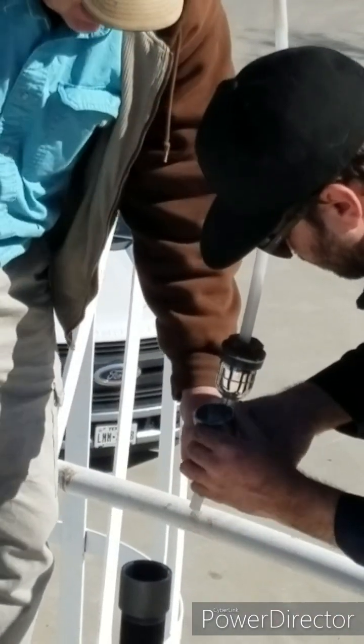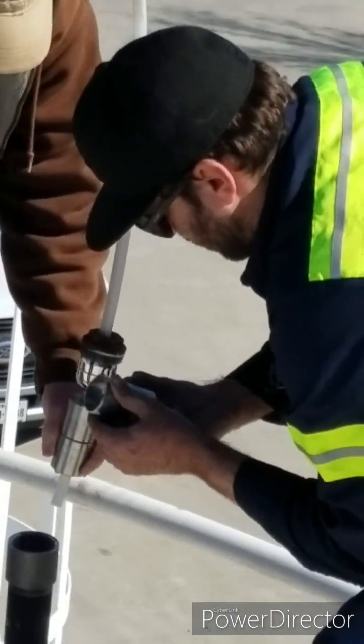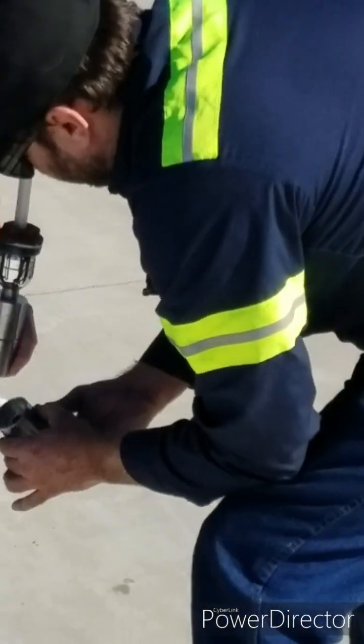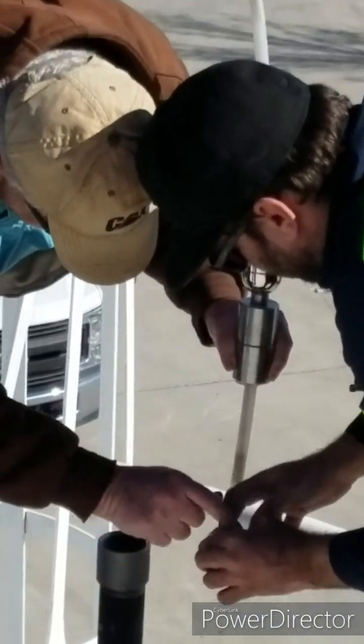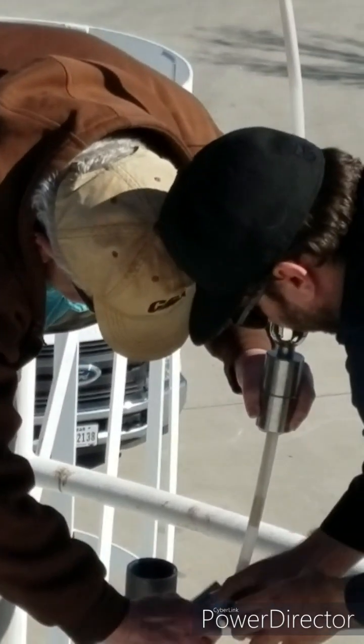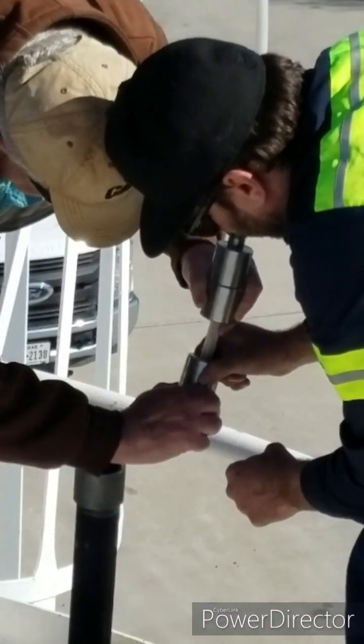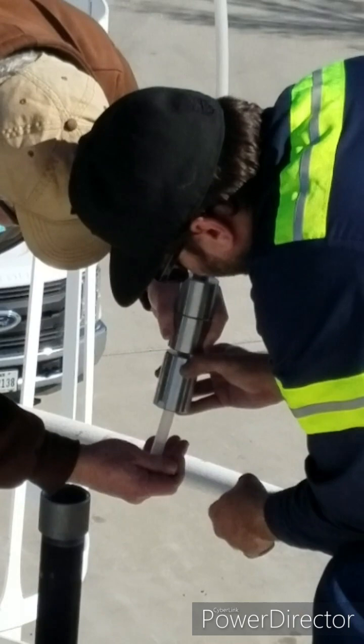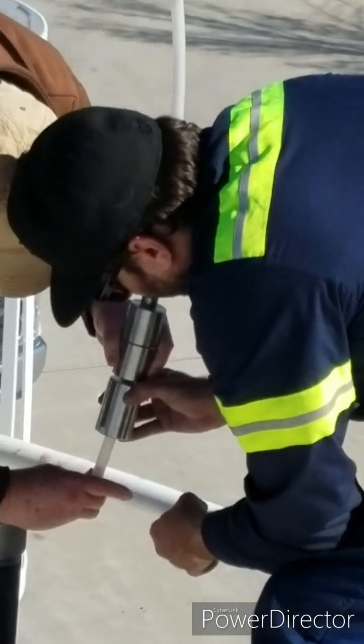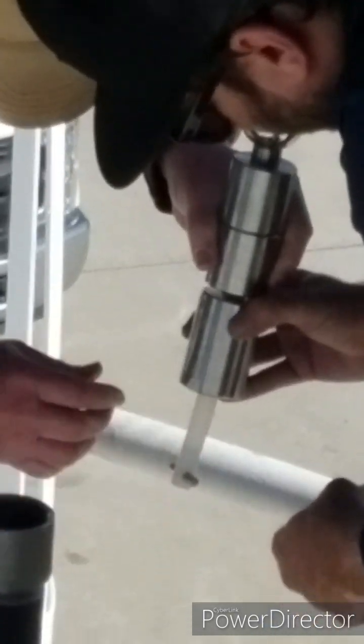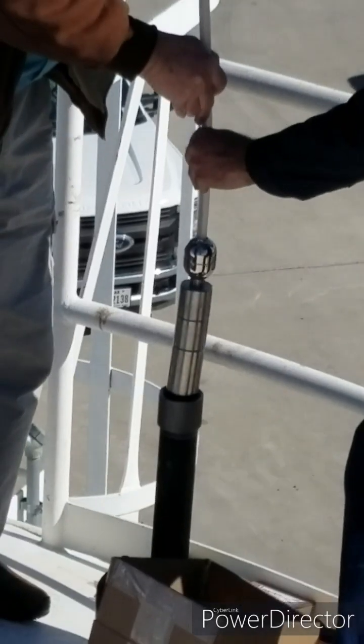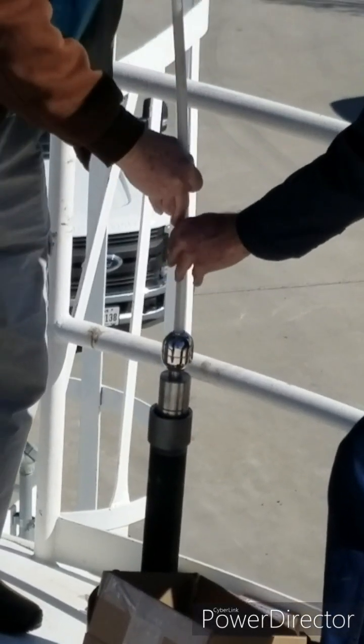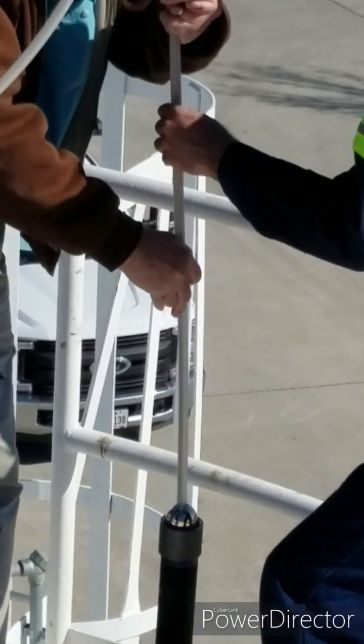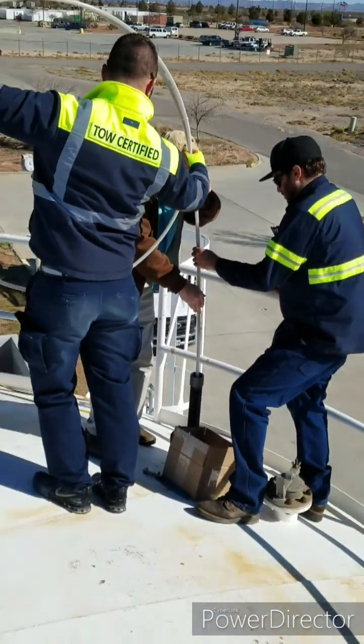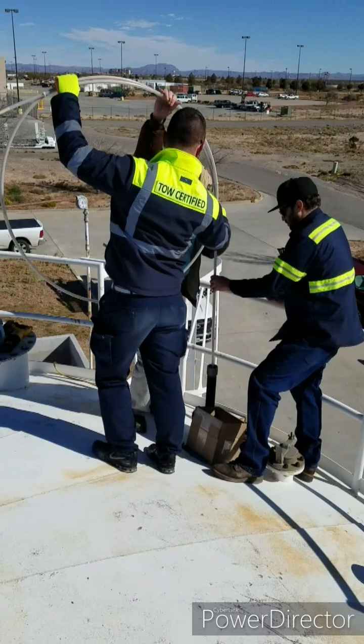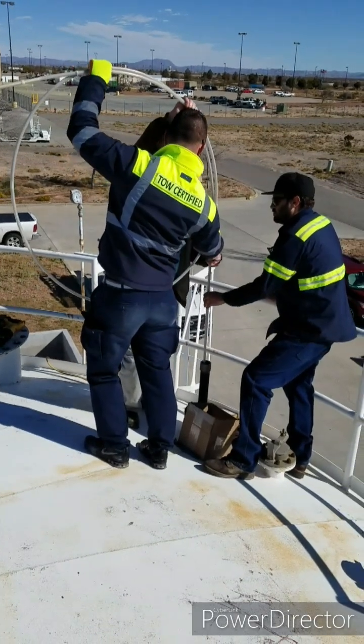The last weight to go on is the one with the concave bottom, and then you'll center the holding pin into the horizontal hole at the bottom of the probe. Once this is complete, you are ready to insert the probe into the tank. Care should be taken at this point in handling the probe to keep the metal mounting bushing from sliding down into the floats and weights, as well as keeping the probe straight while lowering it into the nipple pipe.